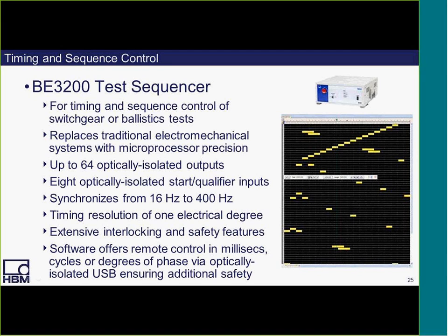to ensure additional safety to equipment and personnel. Now, on this test sequencer, you also have the ability to synchronize from 16 hertz to 400 hertz. The timing resolution is 1 electrical degree. There are extensive interlocking and safety features available on the system, and software offers remote control in milliseconds, cycles, or degrees of phase via optically isolated USB, ensuring additional safety. Now, on the right, you can see a sample overview of the software where you can set the timing of every optically isolated output.